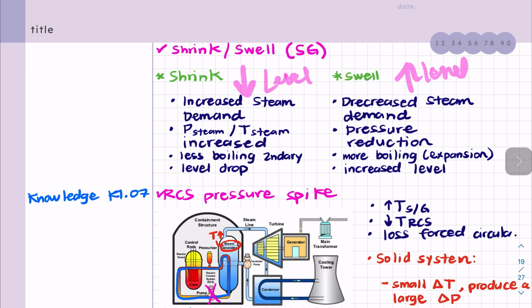Then we have swell. Swell is a decrease in steam demand - we see the opposite, a pressure reduction. We have more boiling, meaning an expansion, which is what's meant by swelling, and that creates an increase in the water level as well. So shrink lowers the level - that's important. Swell increases the level - that's something important to remember. As long as we remember that, we remember the basics of it.